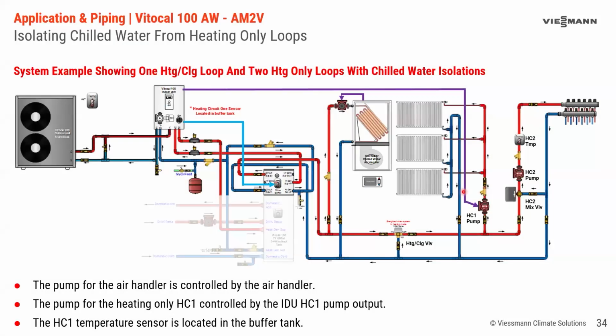So now we look at an even more complicated or maybe more elaborate system. We still have the heating cooling valve here, but we have circuit one broken into two groups. We have the air handler, which has its own pump. We have the panel rads, which are going to use the heat cool circuit pump. Now, this is going to be calling for heat and it's going to run the pump whenever this is in that mode. And this is going to run the pump for heating and cooling.